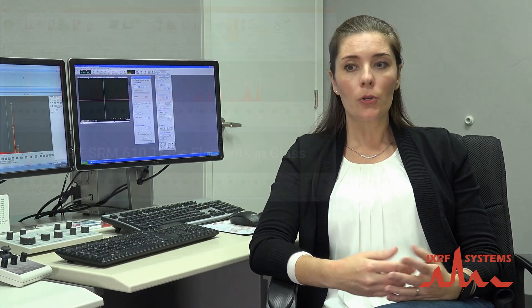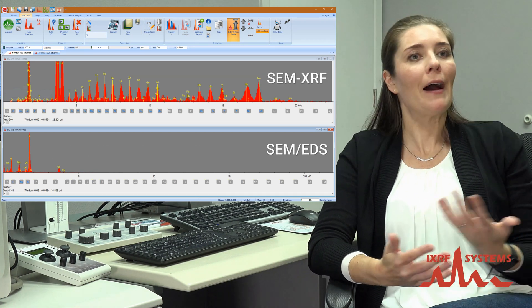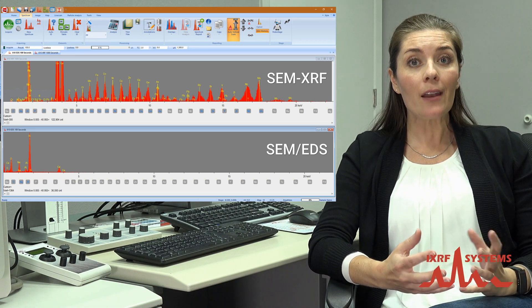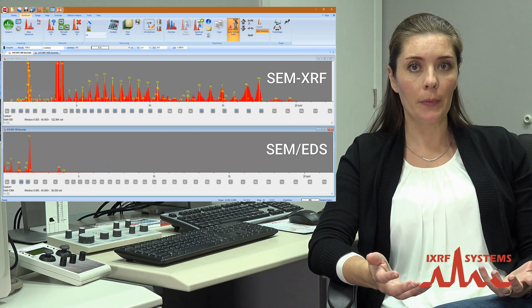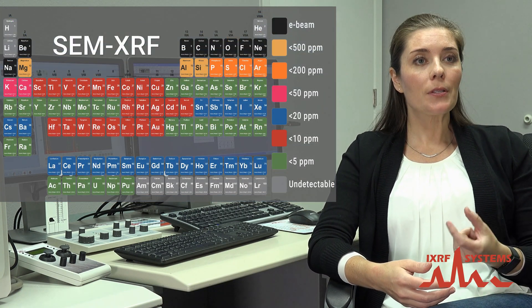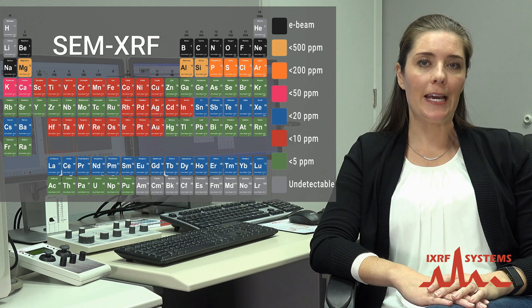So why should I consider adding an XRF source to my SEM? Let's say you have a sample and you're analyzing with EDS, then you hit it with XRF — you might realize there are five elements in your sample you had no idea were present because they're below the limits of detection of your EDS. We see this a lot in glass. A perfect example is the NIST 610 glass: if you hit it with your E-beam, we're seeing about five elements — what you'd expect in glass, like calcium and silicon. But if you hit it with XRF, there are about 15 elements we had no idea were present. With XRF, we're able to see all those elements in that glass that are about 200 to 600 ppm, well below the limit of detection for EDS.